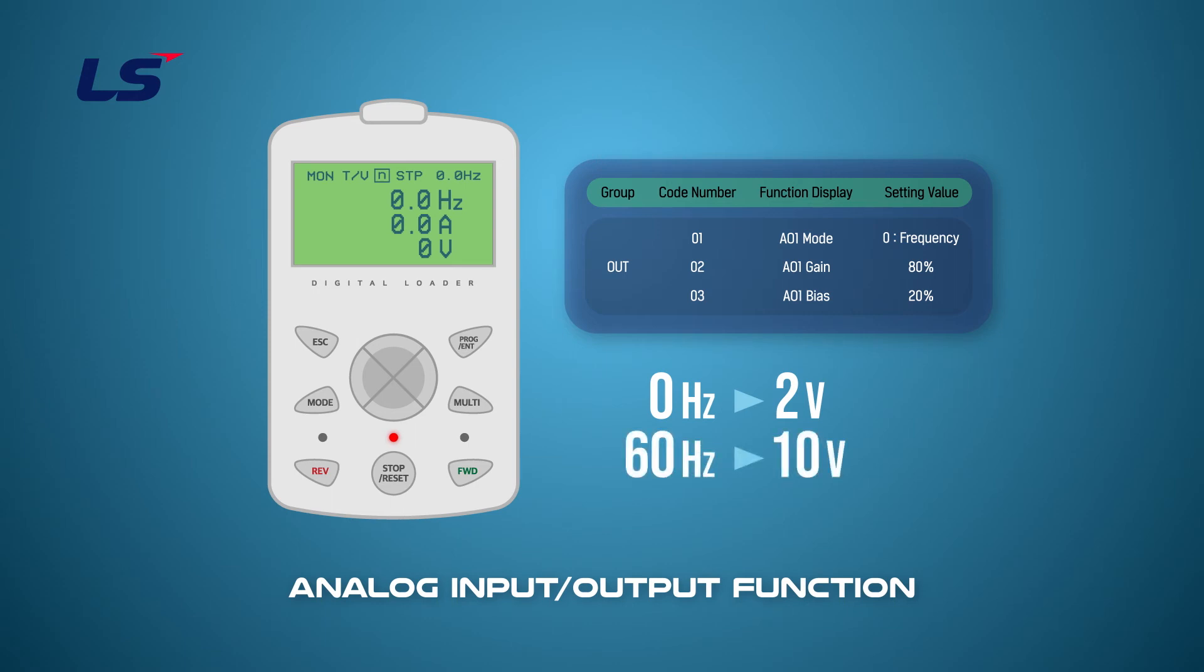First, press the mode key to enter parameter mode. Use the directions keys to move to the OUT group. Select 0 frequency in AO1 mode. Set the gain value for analog output to 80% in OUT group 2 AO1 gain. And bias value for analog output to 20% in OUT group 3 AO1 bias.